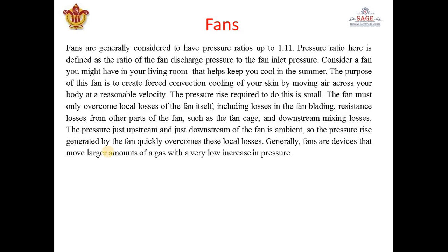Now we have three categories: fan, blower, and compressor. First, a fan is a device whose pressure ratio is up to 1.11. The pressure ratio is the ratio of exhaust (discharge) pressure to inlet pressure. So if the pressure ratio is up to 1.11, it is classified as a fan.